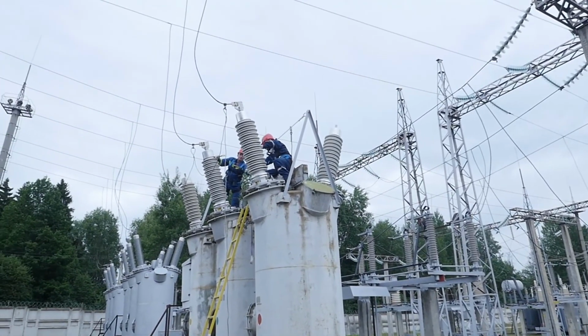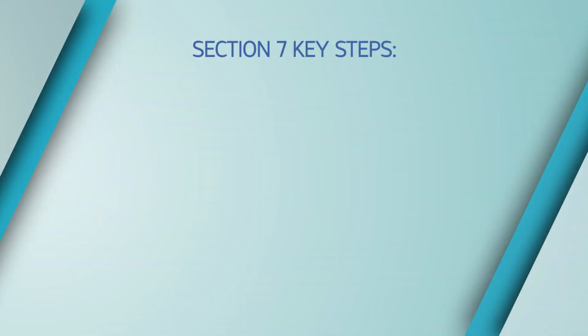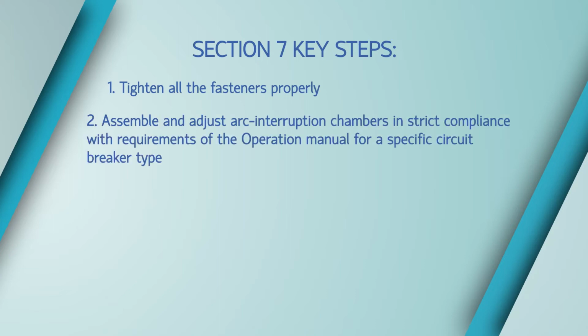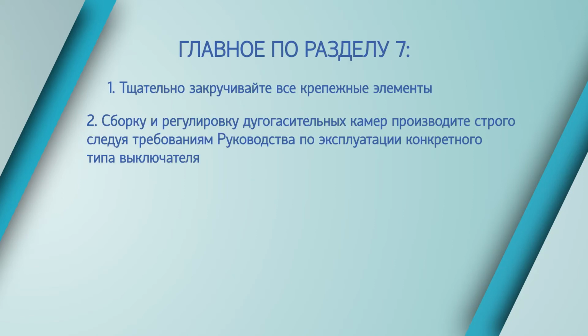Now we have installed the bushing bottom. Let us follow the key steps again. Tighten all the fasteners properly. Assemble and adjust arc interruption chambers in strict compliance with requirements of the operation manual for a specific circuit breaker type.